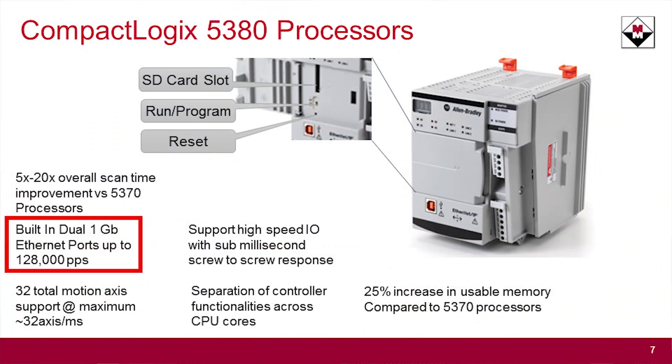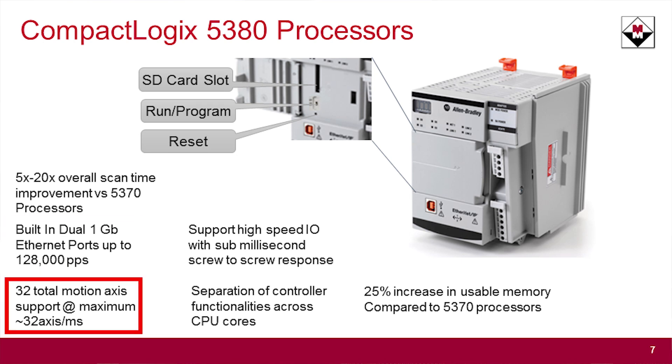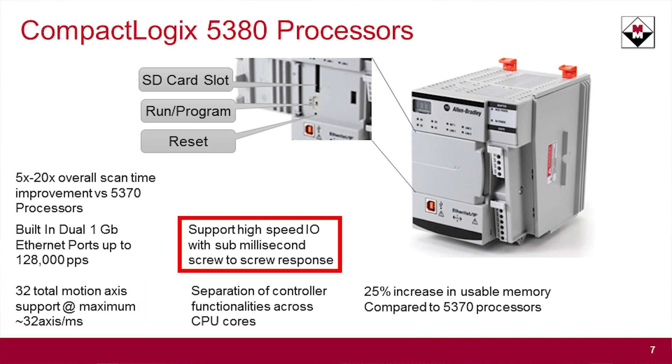It has a dual gigabit port built into the bottom of the L8-based processors. It can support up to 32 motion axes in this platform now over Ethernet. It has the same support of high-speed I/O with sub-millisecond scan-to-scan time as the ControlLogix — this is a big difference between previous CompactLogix and the current ones. In the previous CompactLogix, the basic bus was DeviceNet, so it was limited to 500 Kbps of transmission between the I/O cards and the processor.